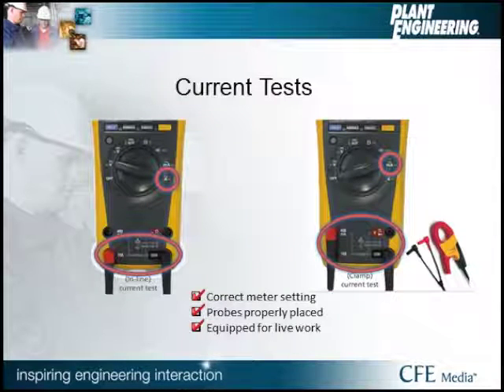If we're going to do current tests, we want to make sure that we recognize that this is extremely dangerous because we're doing this on a system under load. The biggest risk you're going to find is when you move the wiring around so that you can get your clamp around that wire, and the wire can come loose. This can cause a phase-to-phase or a phase-to-ground fault. We want to make sure, again, that our meter is in the correct meter settings, that our probes are in the proper jacks. Again, we have the right equipment for this type of test.